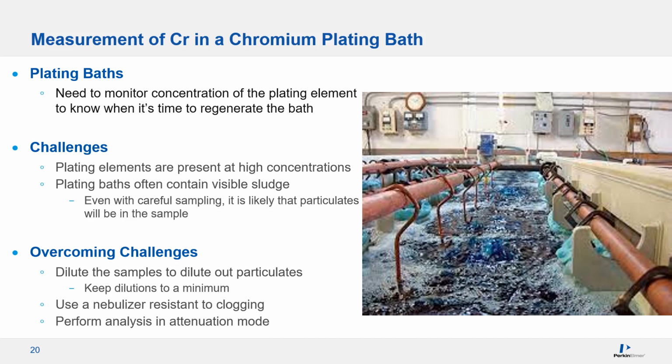In case any particles do make it into the sample, even after dilution, we want to use a nebulizer which is resistant to clogging. And finally, we're going to perform the analysis in attenuation mode to make sure we're on the linear part of the curve.